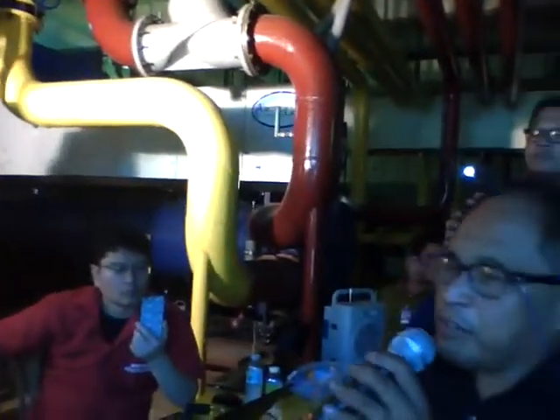In relation to permanent magnet, is there a number of years that we need to replace that magnet? No number of years. There's no number of years. It's a permanent magnet. So unless you run it outside of those design conditions, you should never have to replace this compressor. This compressor is a lifetime compressor.